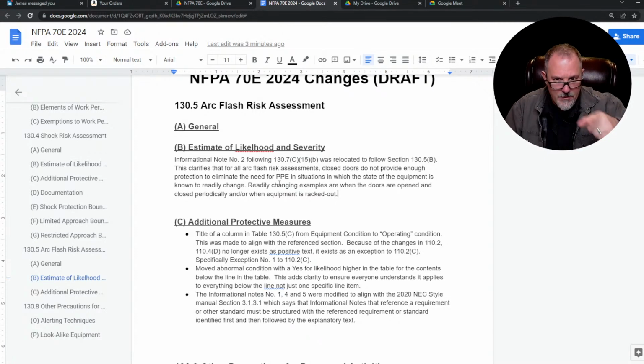And I'm not sure. And then what he says is a common misconception is that even in non-arc resistant equipment, closed doors remove the need for PPE. And it says the informational note relocated clarifies that closed doors do not provide enough protection to eliminate. I still say, and to your point, I think what they mean by state is the condition, because I could understand if the condition of the breaker is not normal for whatever reason. The fact that the door is closed and you're going to open and close it with the door closed does not mean you do not need personal protective equipment.